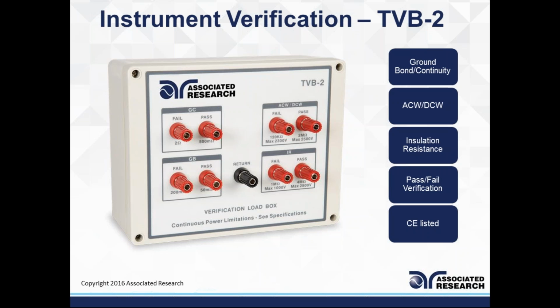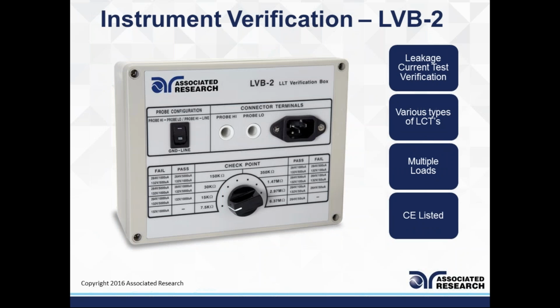The next box we have available is the line leakage verification box. Again, same kind of concept, a pass-fail verification for different types of line leakage tests. Again, this is CE listed as well. It's got different probe configurations, and it will work with line leakage or leakage current test instruments built by Associated Research. Not just Associated Research, but you can use it with other instruments as well, as long as you provide the appropriate connections.